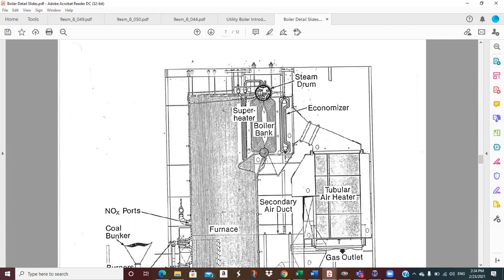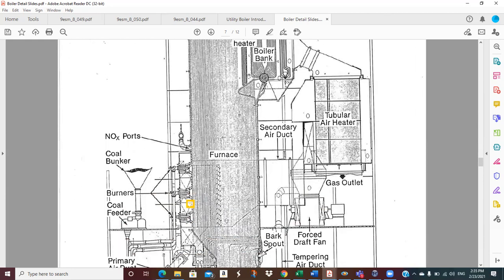And then this boiler bank, this is kind of interesting. This is your main steam drum up here, and this is a lower drum, typically called a mud drum, because if there's any debris or silt, it's going to accumulate in the bottom drum. These are just additional steam generation tubes added so that we can get more steam generating capacity out of the boiler. You can see this boiler is not doing much superheat at all. It's just that one little tube bank right there. But we can generate in the furnace water wall, and we can generate in the boiler bank. Then you see an economizer section to boost the temperature of the feed water before it goes into the drum, then the air heater, and the primary and secondary air ducts, the secondary air duct being for staging combustion.